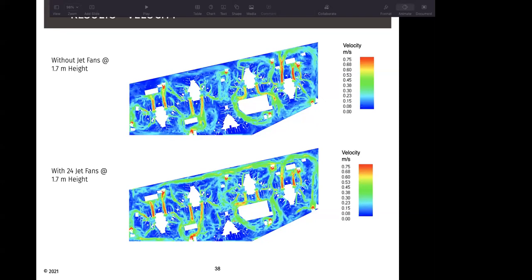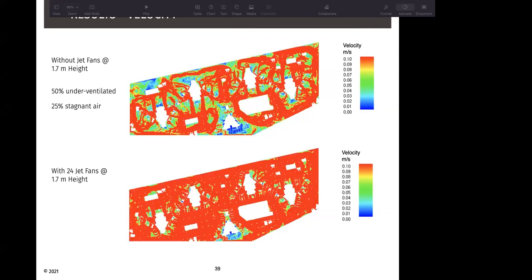So in this case, for the fans working in normal condition, without the jet fans, we can see that there are quite a few blue portions. Now, if I were to adjust the scale to 0.1 meters per second, what we consider as underventilated is when the velocity is less than 0.05 meters per second, and stagnant zone would be when the velocity is completely zero. So anything between green to blue would be considered as underventilated to stagnant zones. So without the jet fans, we can see that there are 50% underventilated zones and 25% stagnant zones in the car park. And we have optimized that with 24 jet fans to reduce the stagnant and underventilated areas.